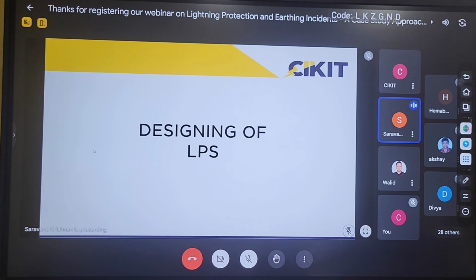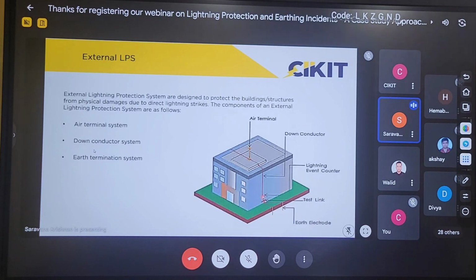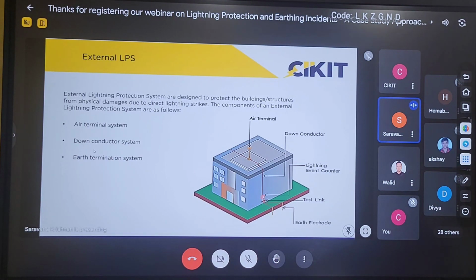If I am performing the designing of a lightning protection system, it majorly contains three main components: the air termination system, the down conductor system, and the earth termination system. The air termination system is the component which intercepts the lightning, the down conductor system acts as a bridge between the air terminal and the earth, and the earth termination system dissipates this energy into the soil.